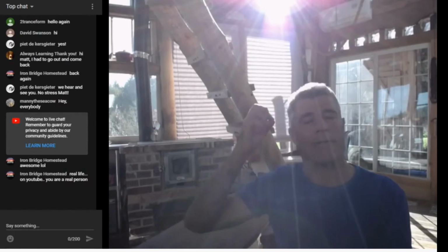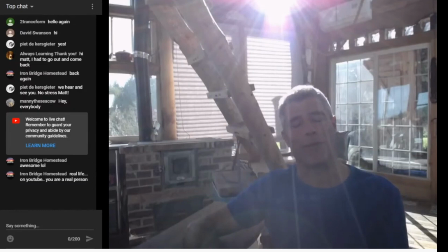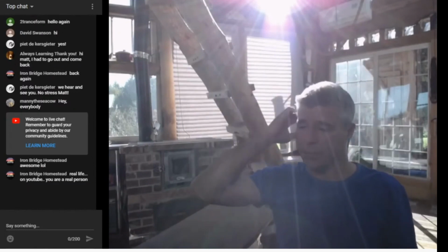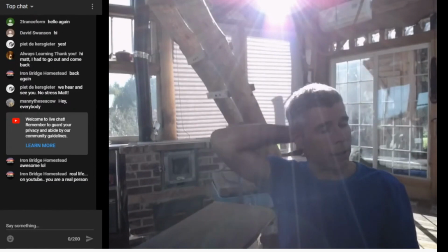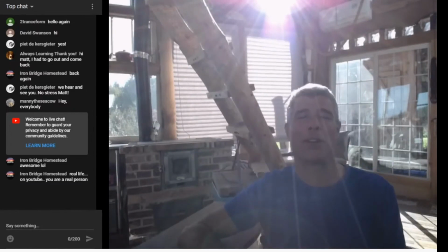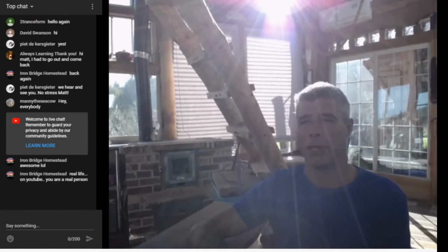And I don't have codes or guidelines right in front of me, but I know general rules. And for the most part, what we want to do is exit as vertically as possible out of the stove. We don't want to descend after the stove at all. We'd like to just try to ascend. And ideally, we try and ascend with as little diversion from our main direction, our main goal, as possible. So we don't want elbows if we can avoid them.